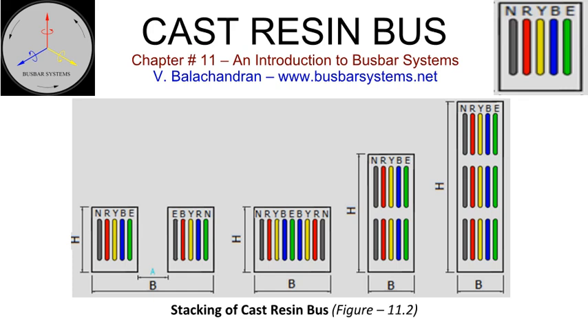Some data centers require a neutral conductor that is double the size of the phase conductors due to high harmonic contents. Low-voltage cast resin bus does not require a dedicated metallic enclosure. Protective earth conductor may be cast, or external earth may run along the length of the cast resin bus to provide a low impedance path for a ground fault current.